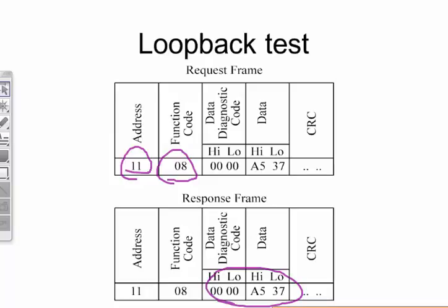Yes, I am. So this will work even if you get your addressing wrong, because in ModBus, I've had devices out there where if you don't ask it for exactly the right function from exactly the right address, it won't even respond. It just ignores you. It's an EDMI electrical meter.